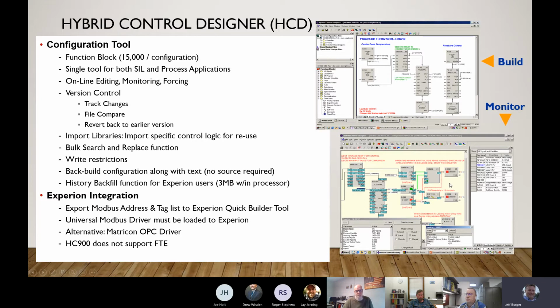It also allows online monitoring of the system. So the same configuration tool is used for assisting in troubleshooting and diagnostics, because you can have the software communicating to the HC900 in real time, and you can watch all of the analogs and the digital values, and the blocks go live or go offline when they're not utilizing that control scheme. So for startup and troubleshooting, this is a very powerful tool because it allows you real-time data as you're trying to start up or troubleshoot a situation out in the plant.